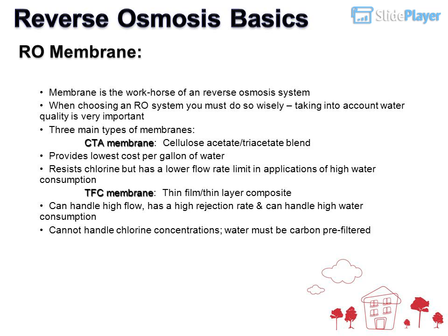TFC membrane, thin film/thin layer composite. Can handle high flow, has a high rejection rate and can handle high water consumption. Cannot handle chlorine concentrations, so water must be carbon pre-filtered.